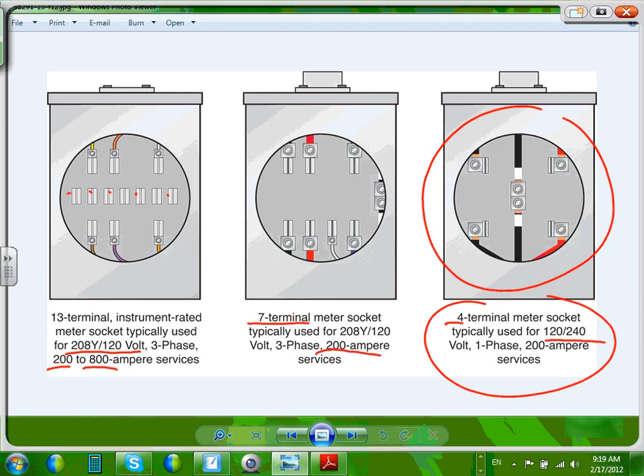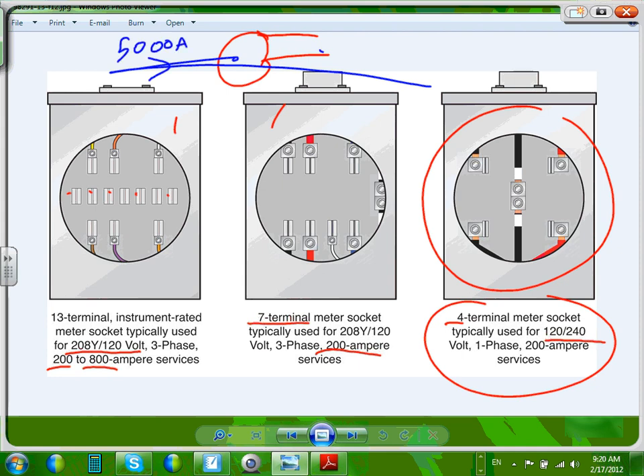Here you're using some type of CTs and PTs in these areas. Here you're directly measuring the equipment. So different types. Most of the time, guys, in a commercial building we have a CT that converts. You put a CT here, and you bring a feeder inside it. You put the feeder inside it. So this is carrying 5,000 amps. I'm exaggerating here. This will be seen as 5 amps. So like a current transformer, it transforms the current from one very high level into one very low level, so you can measure it. A couple of metering options.